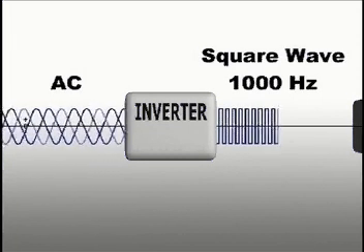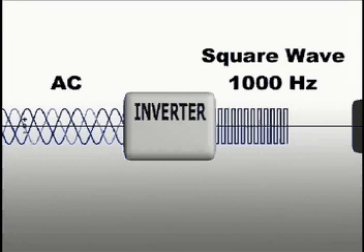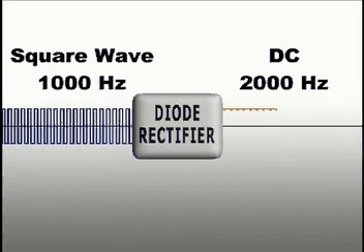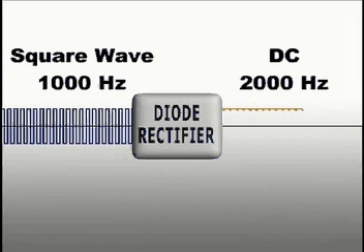Square waves can be controlled better than sine waves, allowing higher operating frequencies. For example, a three phase DC spot welder that uses the older technology delivers 180 cycles per second. ProSpot's PR2000 uses inverter technology and operates at 2000 cycles per second.